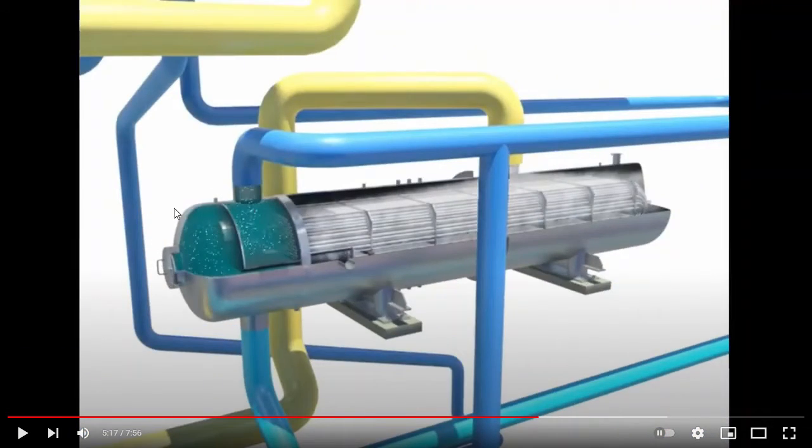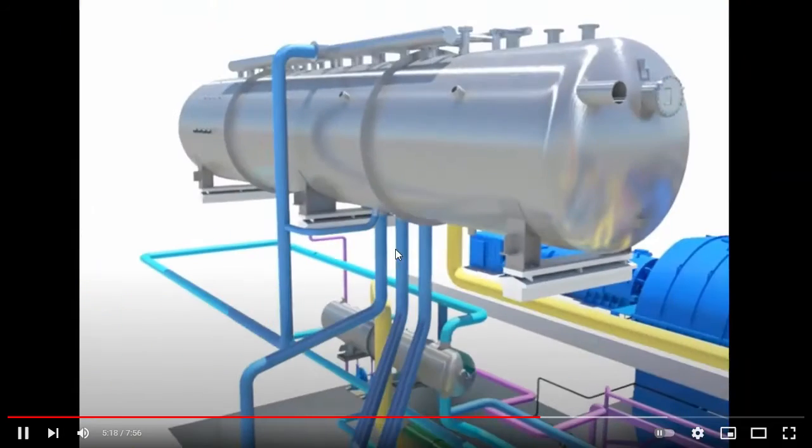On the way up there, it goes through these heaters, which I don't think Bailey talked about, so we won't hit on them. But basically, they heat that water up as it goes up. That way it doesn't hit the drum at 100 degrees or something, right? And we're trying to get it up to 1,000 degrees. So we do it to kind of not thermal shock, and it also has another benefit. But you don't have that in your video, so kind of ignore what I just said. But anyway, so that water gets pumped all the way back up into the drum.